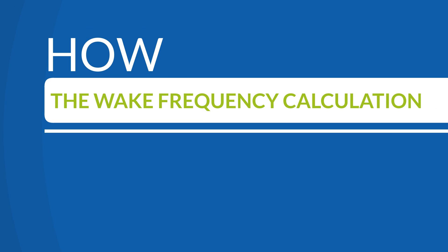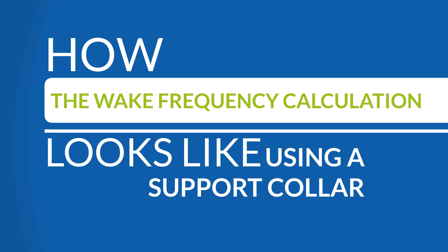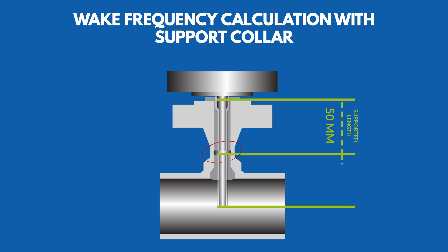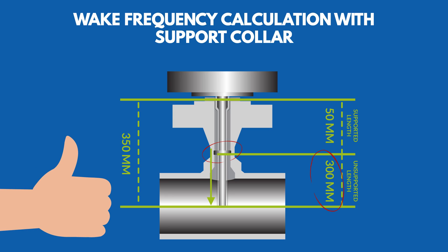Let's see how the wake frequency calculation looks using a support collar. A support collar is set at 50 mm away from the flange of the DBB valve. This portion is now considered as the supported length. The portion below, with a width of 300 mm, is considered as the unsupported length. The calculation starts from the support collar onwards to the end of the probe. Having an unsupported length of probe at 300 mm, it is now within the recommendation for the wake frequency, and the overall length of the probe of 350 mm can be used as required.